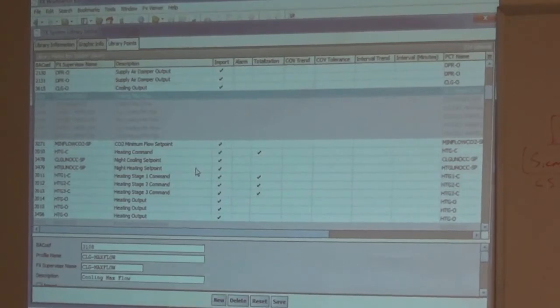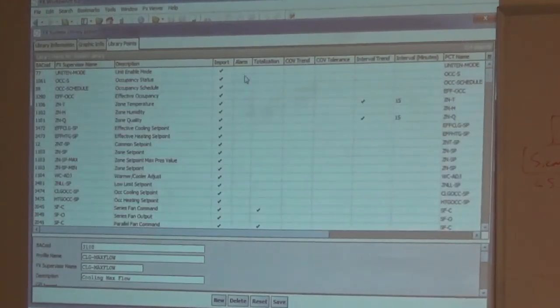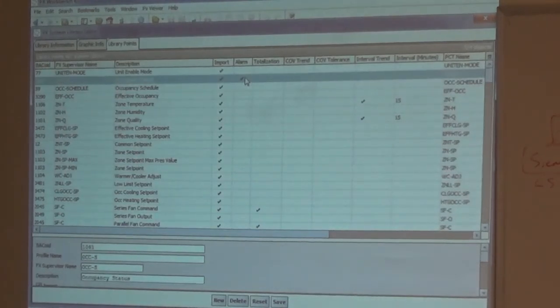How many points do you need for a VAV box? I don't know, it's debatable. But anyway, every time I want to bring in one of those, I checkbox import and it automatically brings that point in every time. If I want to add an alarm to something, I add an alarm to it.